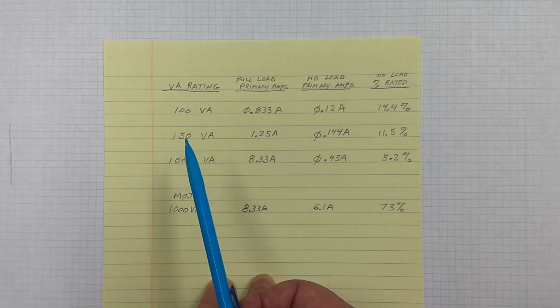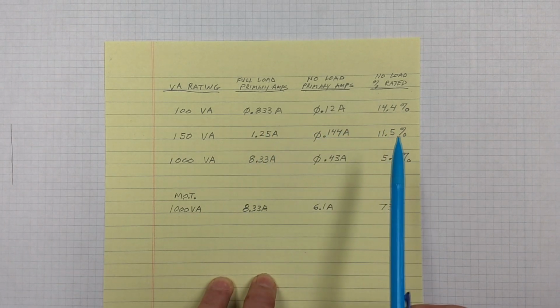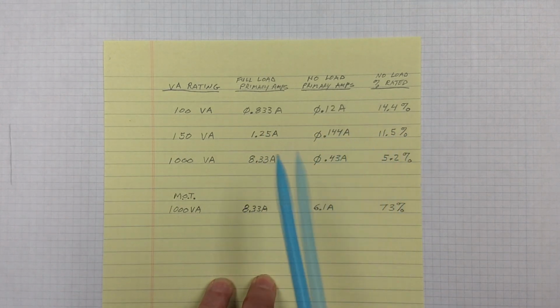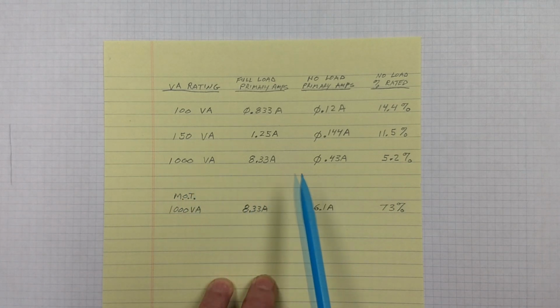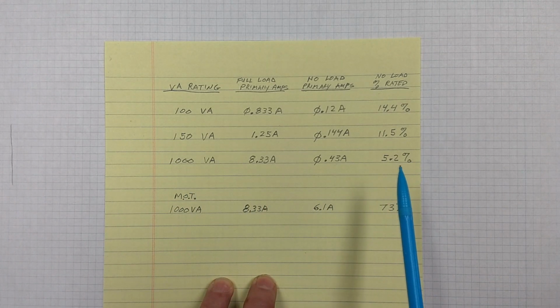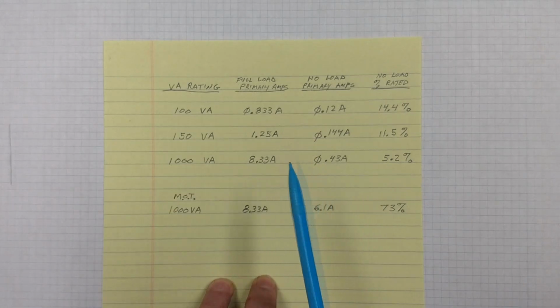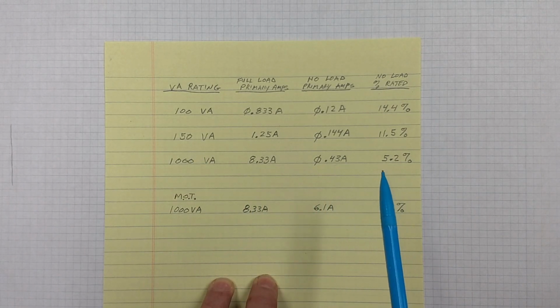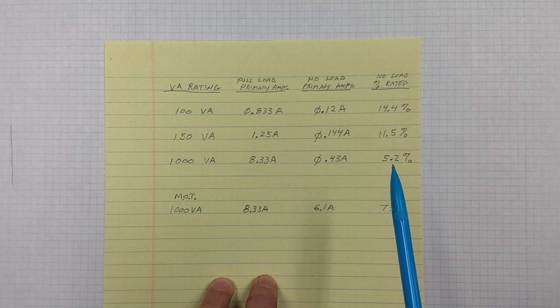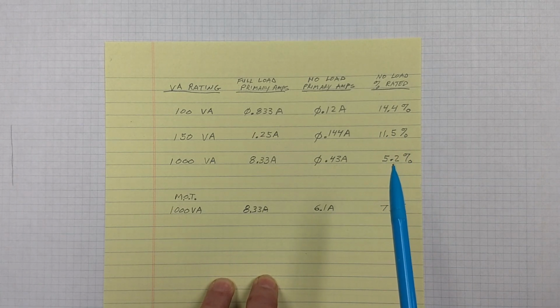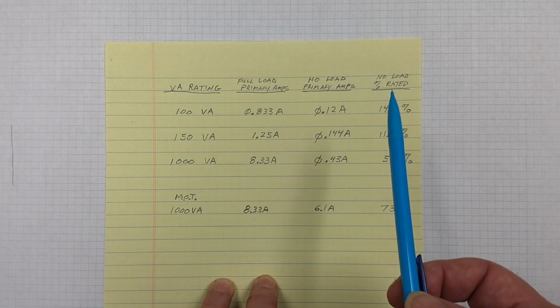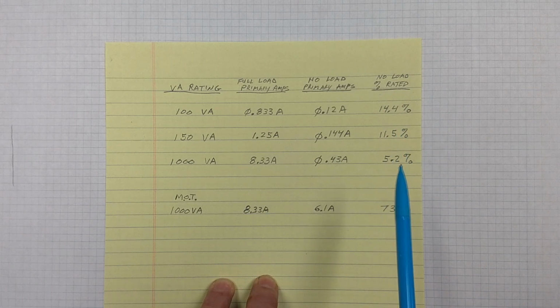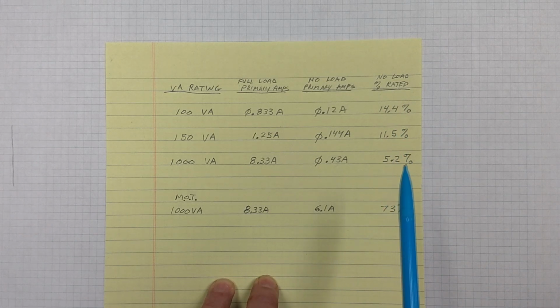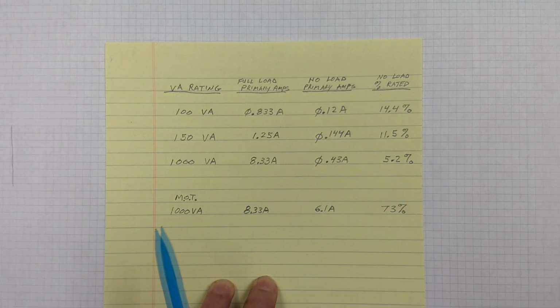And on a slightly bigger transformer, the number's a little lower, and in a bigger transformer it goes down some more. So as the transformer size goes up, they tend to use more iron and copper, and to try and keep not only more efficiency in the transformer, but also it ends up with a lower no load or magnetizing current.